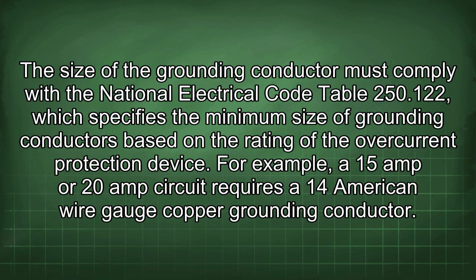The size of the grounding conductor must comply with the National Electrical Code Table 250.122, which specifies the minimum size of grounding conductors based on the rating of the overcurrent protection device. For example, a 15 amp or 20 amp circuit requires a 14 American wire gauge copper grounding conductor.